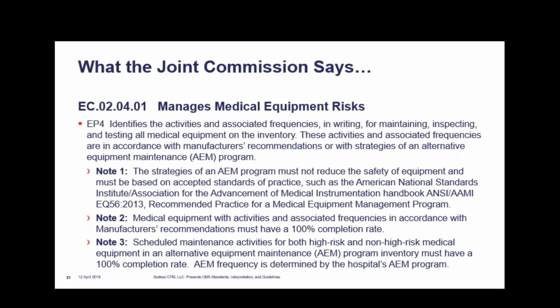It's tremendous. So I think that's easier to do for the hospital than the manufacturer, and there's less liability. And I would just say that utilization is a great factor. You can track it, you can do it. Mine's more around criticality, right? And criticality is defined in many ways. If I only got one defibrillator in the entire hospital, that could be pretty critical. If I got 75 of them, maybe not so much. If I got one CT, it's in the ER, could be pretty critical. So criticality to me takes more of a role than utilization per se.